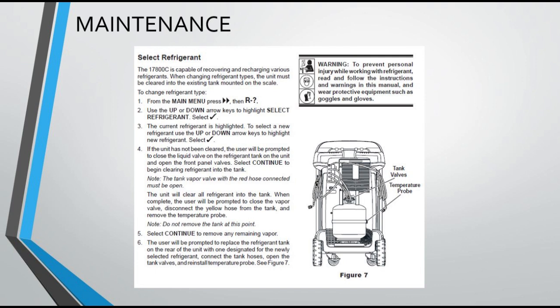Select refrigerant. The unit is capable of recovering and recharging various refrigerants. When changing refrigerant types, the unit must be cleared into the existing tank mounted on the scale. To change refrigerant type: 1. From the main menu press, then R-?. 2. Use the up or down arrow keys to highlight Select Refrigerant. Select. 3. The current refrigerant is highlighted. To select a new refrigerant, use the up or down arrow keys to highlight the new refrigerant.